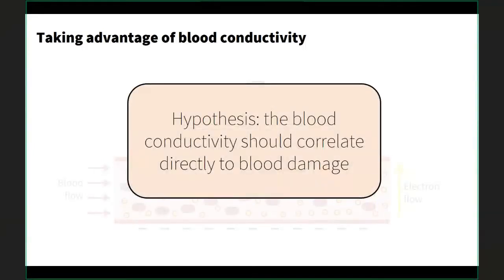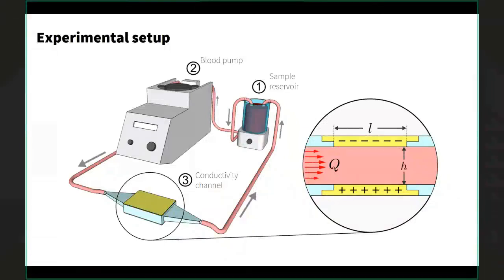Our hypothesis was that if blood is being damaged, the conductivity of the blood should correlate directly to the degree of blood damage. To test this, we designed a benchtop experimental setup — a simple blood pump driven by a peristaltic pump, representative of what's common in dialysis machines. We had a reservoir holding our working fluid, which was porcine (pig's) blood. The blood passed through a 3D-printed microchannel with conductive walls, and we monitored resistance across two conductive plates to get a conductivity measurement as blood flowed through.